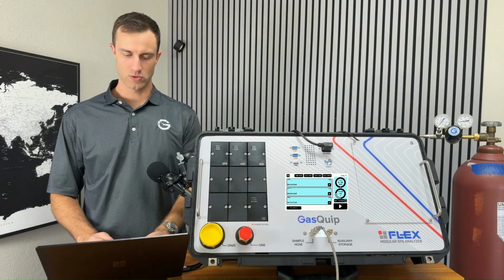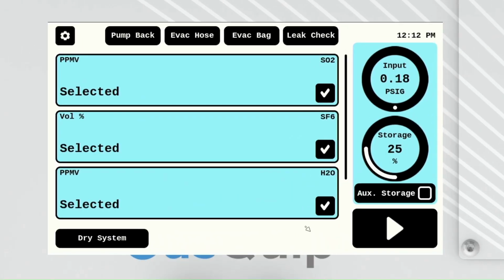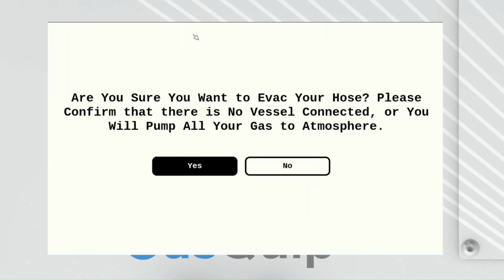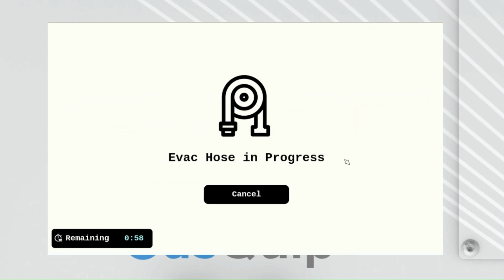If we go back to our analyzer close up, you see that our input pressure is 0.18 psi up here, PSIG. We're going to run an evac hose. It's going to ask us, are you sure you want to evacuate your hose? Please confirm that there is no vessel connected, or you will pump all your gas to your atmosphere. So we don't want to do that. We have nothing hooked up to the other end of the hose. So we'll click yes, and then the hose evacuation is going to run.